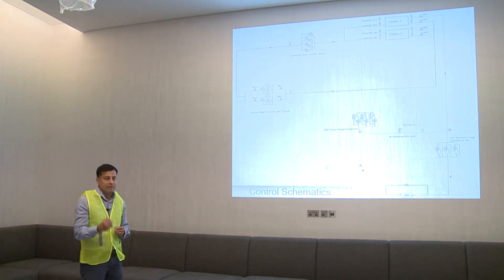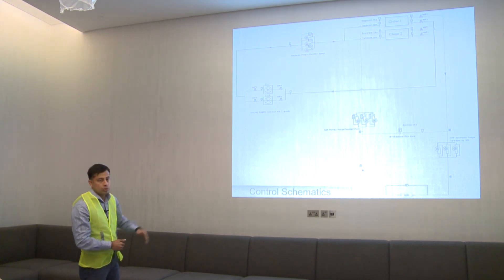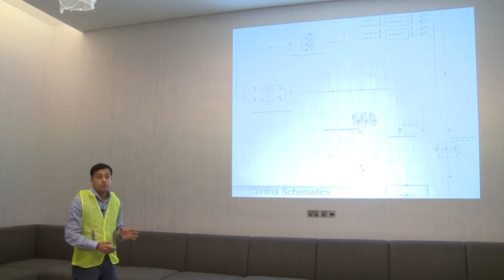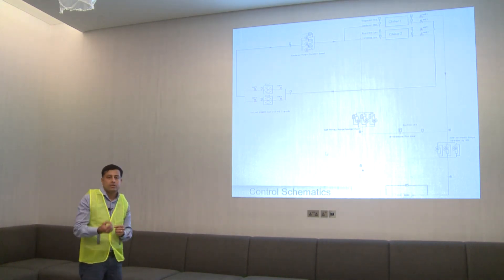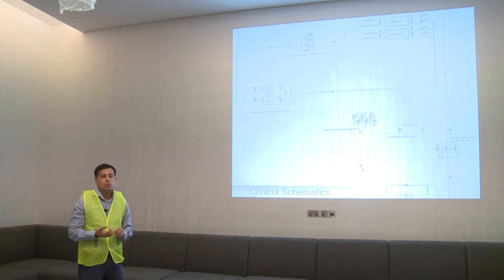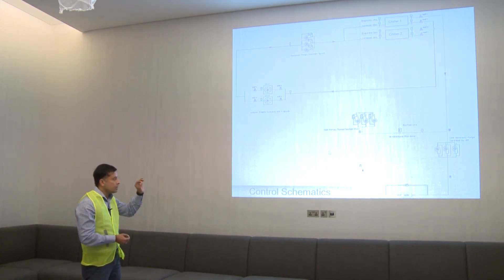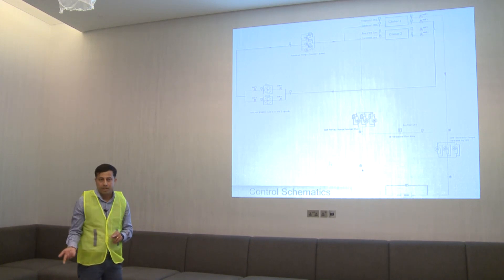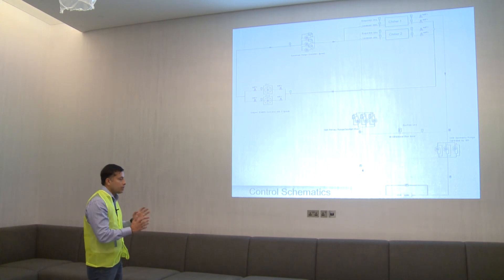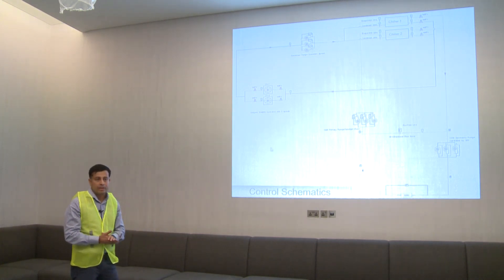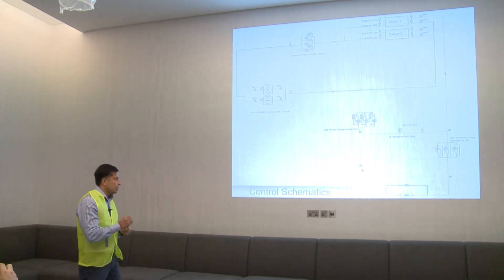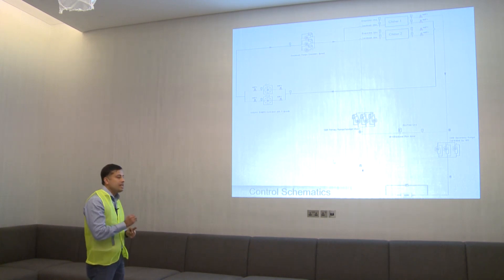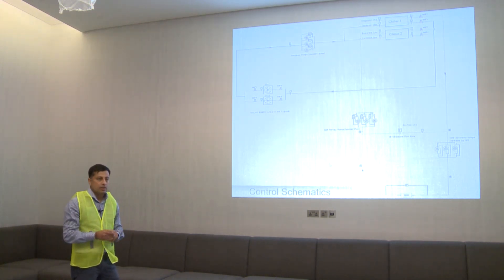All your equipment like AHUs and FCUs are selected based on 5.5°C supply temperature. If you deviate from this set point, the efficiency of the system will reduce. It does not mean that if you increase your temperature, you are reducing energy consumption — that is not correct. If you are using your system effectively, energy reduction will happen automatically. You must keep your supply temperature at 5.5°C, which is the system design temperature. Deviating from that will impact the system and cause issues.